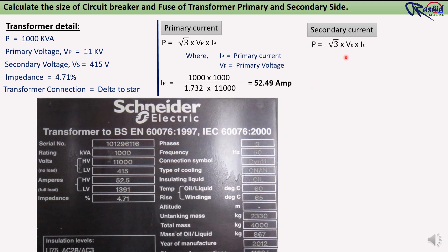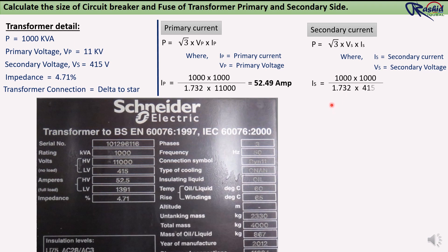The same way we will calculate secondary current. P = √3 × Vs × Is, where Is is the secondary current and Vs is the secondary voltage. Putting all values: Is = (1000 × 1000) ÷ (1.732 × 415) = 1391.24 ampere. You can see the primary and secondary currents written on the transformer nameplate match our calculation: 52.49 A and 1391.24 A.